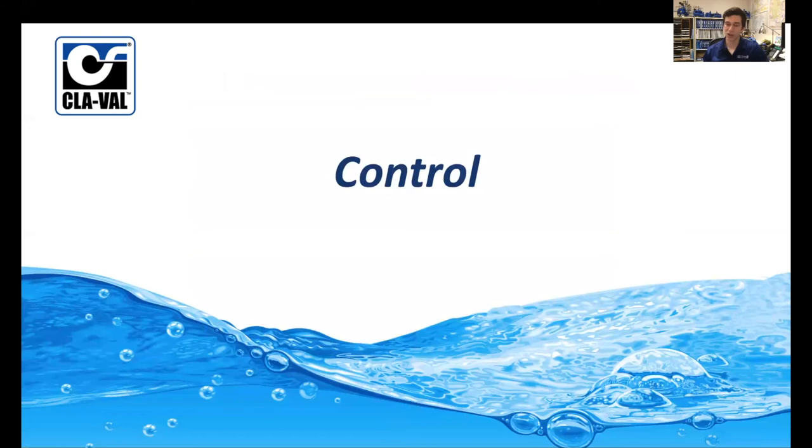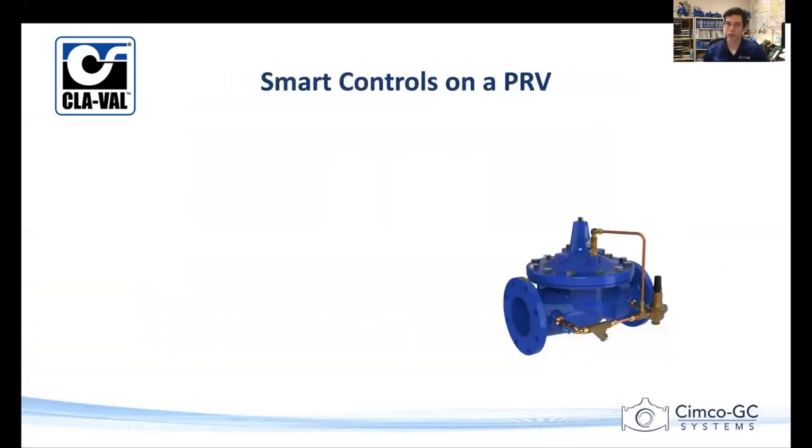The next thing beyond this data and communication and power is control. This would be remotely controlling our valves. So a general pressure reducing valve, you're gonna set the set point with the spring physically, walk away, and the valve's gonna maintain that set point. It's not telling you what it's doing. It doesn't care about upstream or flow. It's just gonna maintain that set point based on its hydraulic system. If you wanna change that, you're gonna have to go down there and get in that vault and change that set screw.